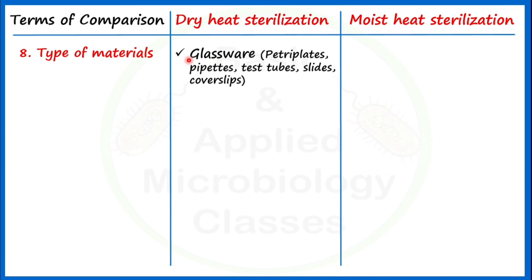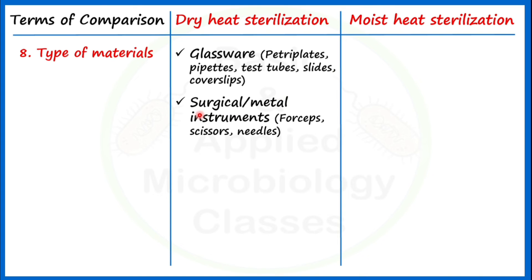The eighth point of difference is the type of materials. Dry heat sterilization is generally used to sterilize glassware such as Petri plates, pipettes, test tubes, slides, and cover slips. It is also used for surgical metal instruments like forceps, scissors, and needles. Additionally, oils, powders, and waxes are sterilized by dry heat sterilization.